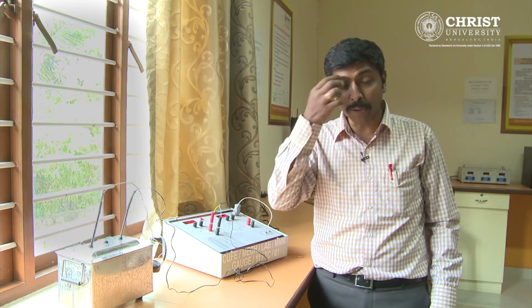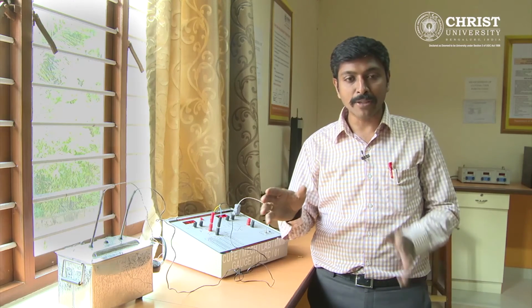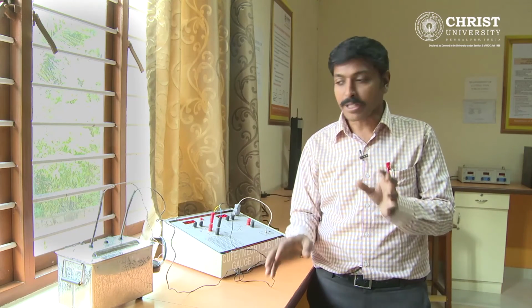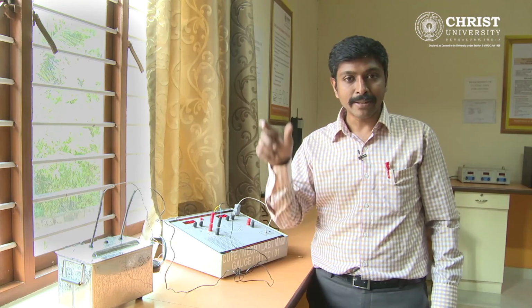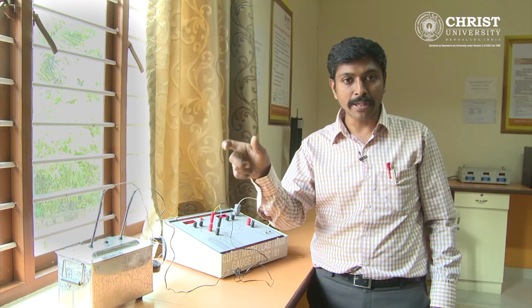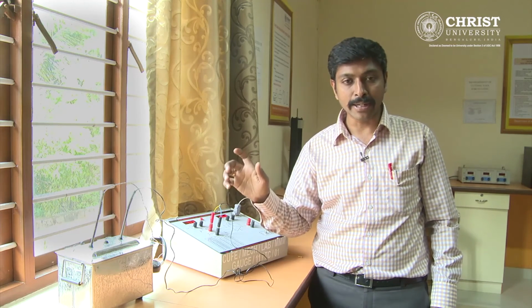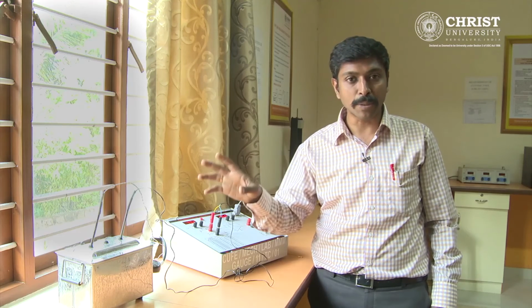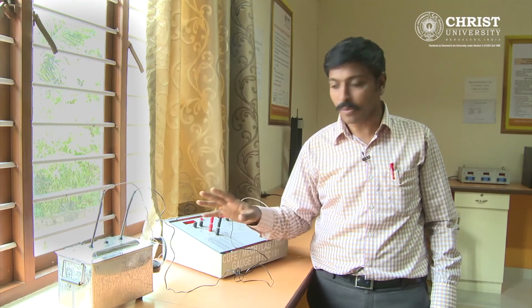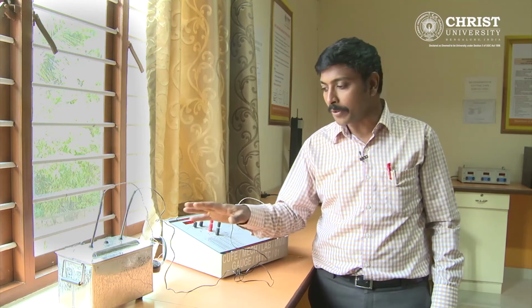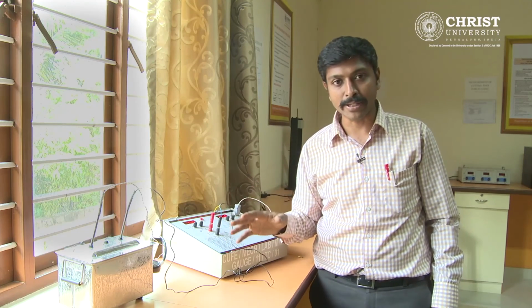J-type thermocouple efficiency can be found out by the following formula: the measurement reading of the thermocouple minus the experimental reading which we get from the RTD, divided by the experimental reading of the RTD. That will give you the percentage of deviation. With that your experiment will be over. You have to repeat the same procedure for 5 iterations.